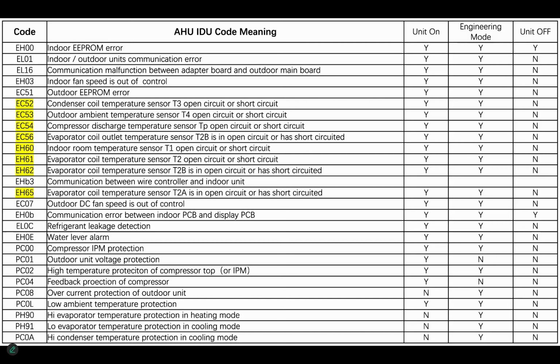All right, EL01. We'll go over the most common ones here. EL01 is an indoor-outdoor communication error. The only way you're going to figure out where the problem actually lies is by using the Dr. Smart, because that is an RS-485 communication signal. You can't see it without an oscilloscope, and you might see some fluctuation, but it doesn't mean anything. So the only way to truly track down an EL01 error on this system is using the Dr. Smart.